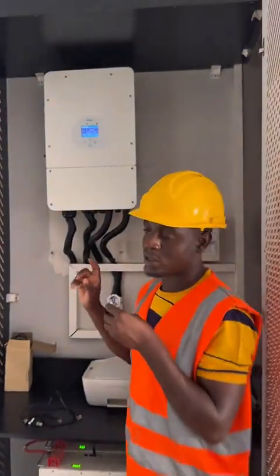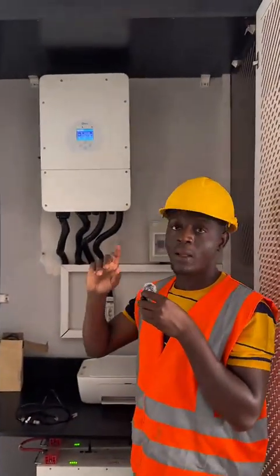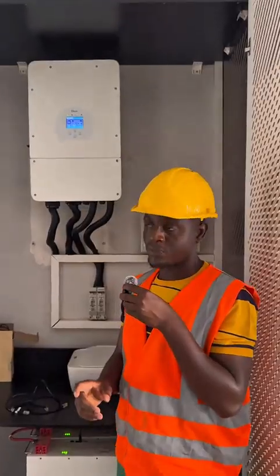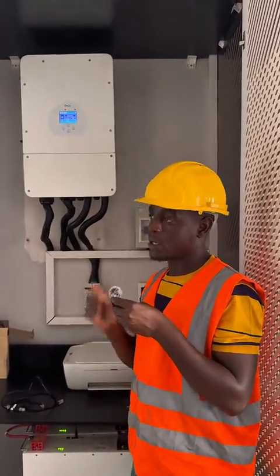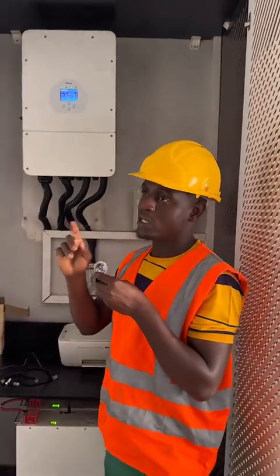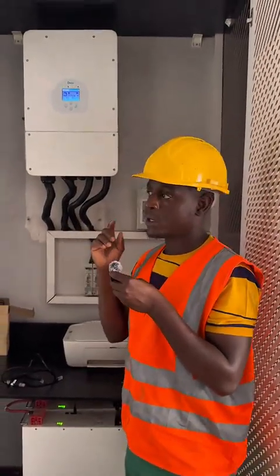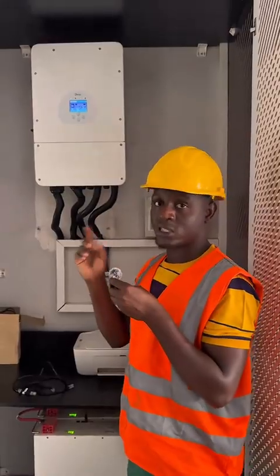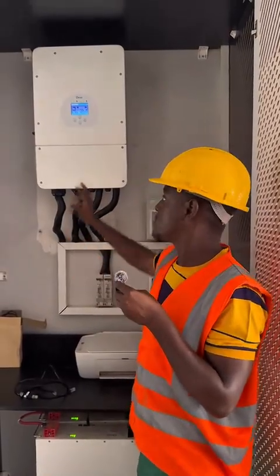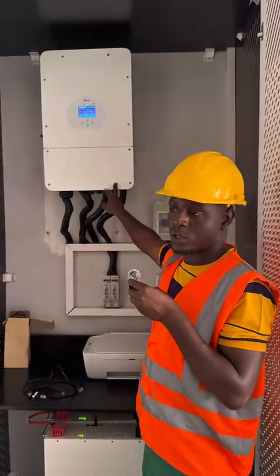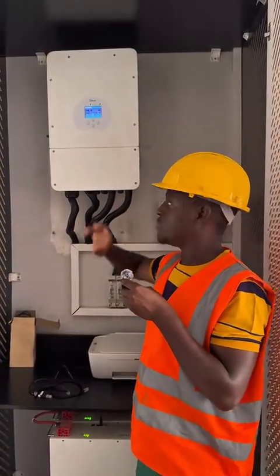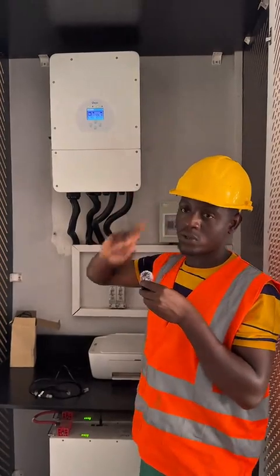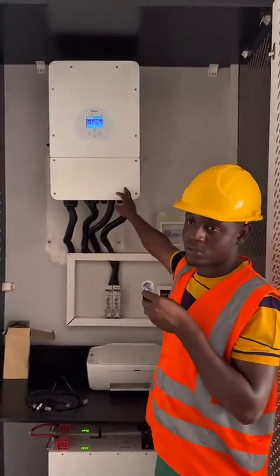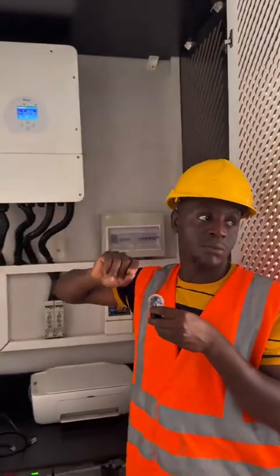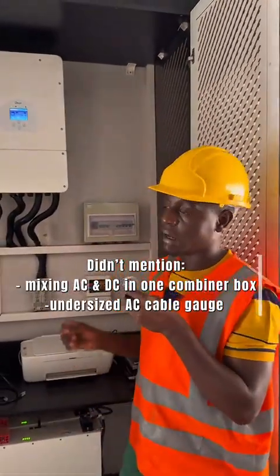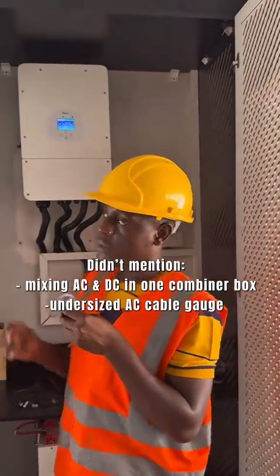whenever the inverter is operating in battery mode, the problem that happens is that when the client connects a kettle, a small kettle, and the microwave - not at the same time, one after the other - this inverter always trips. Whenever the client connects a kettle, the inverter trips. Whenever the client connects a microwave, the inverter trips. So that's the main problem the client told us before we came here.